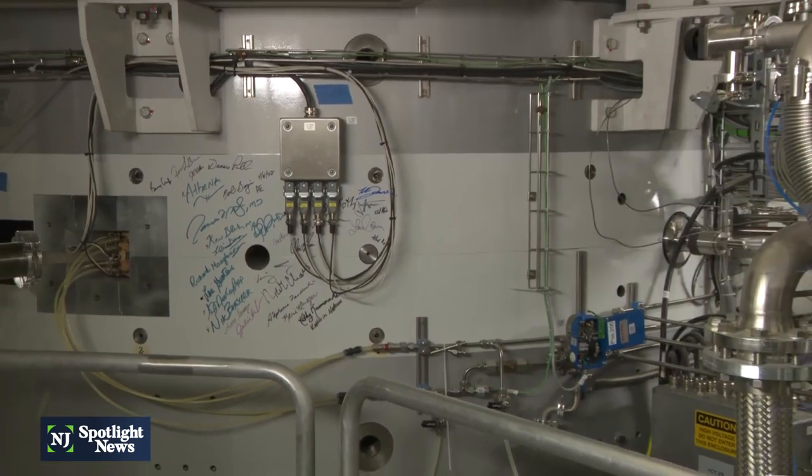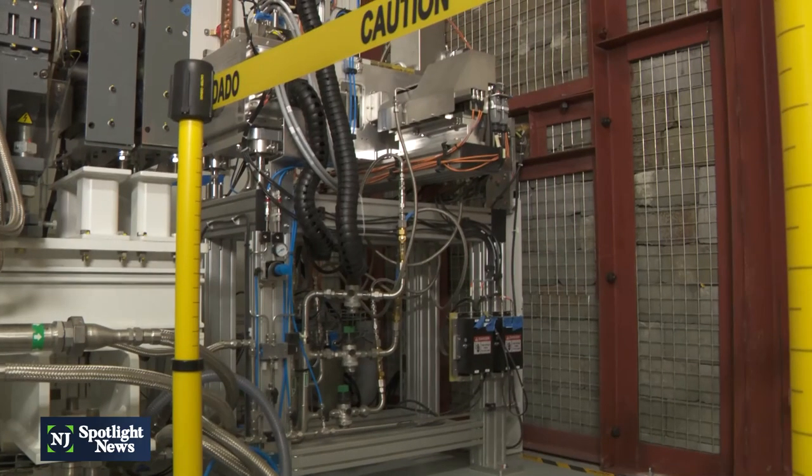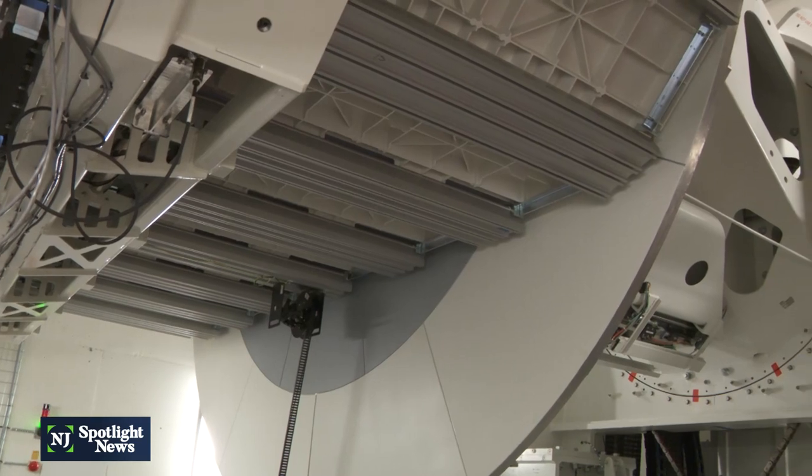So what you're looking at is the cyclotron for the proton system. What it does is it actually speeds up particles to 2/3 the speed of light before we can extract the beam out this little tube down here. And it'll go out through our degrader. We can select the different energies to be used before it enters into the treatment vault to treat the patients.